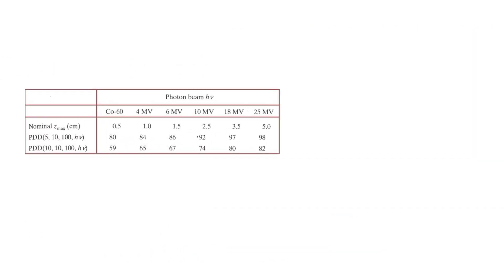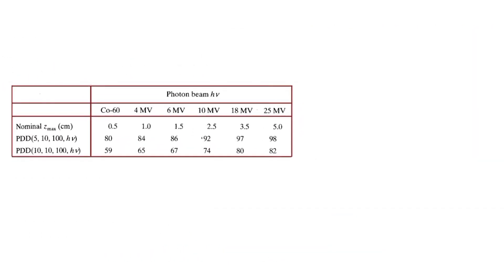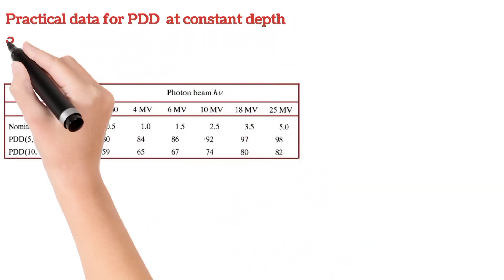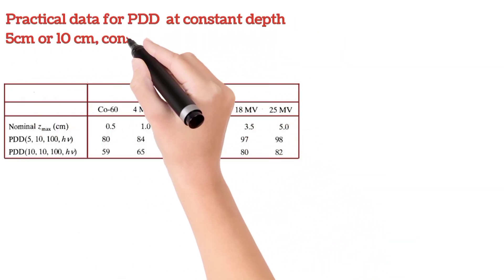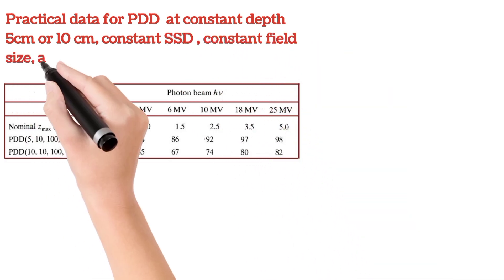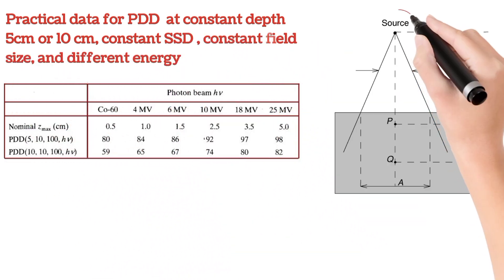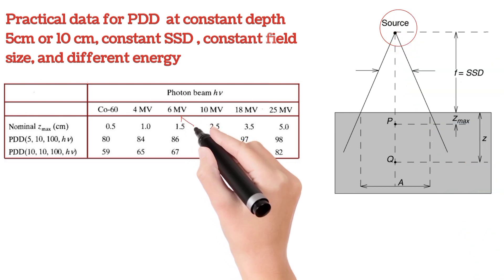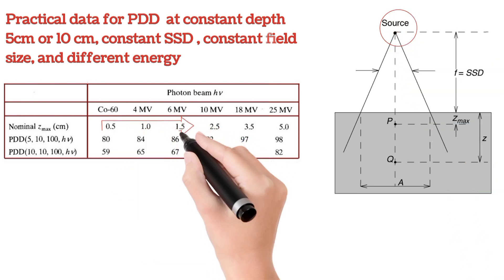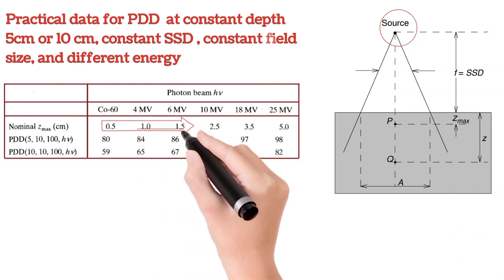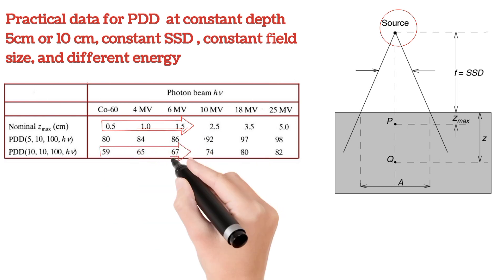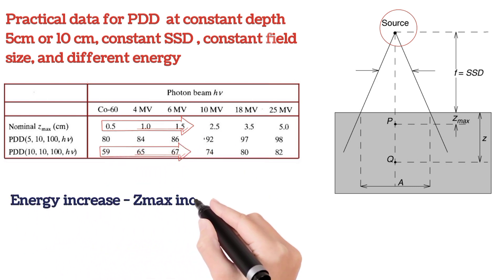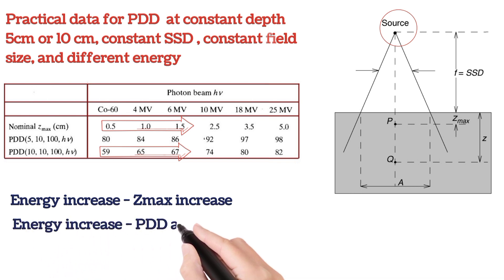This is the practical measured data of PDD at a fixed depth, constant SSD, and constant field size. For different energies, you observe that Z max increases when energy increases. PDD and Z max are directly proportional to beam energy.